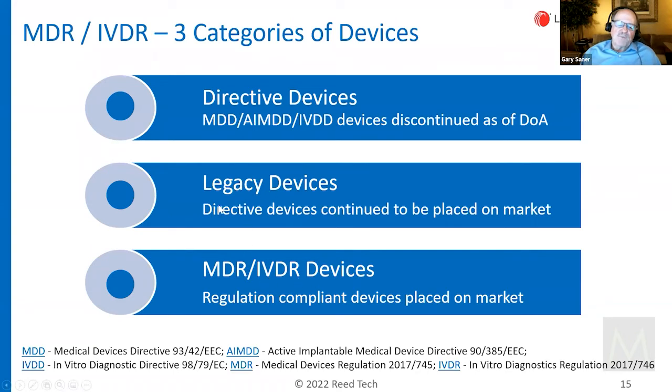So your exact same product can be applied and put into this MDR medical device regulation category. And that's called an equivalent device. So you don't make any design changes, it's physically the same, everything's identical, but now it meets the regulations. You might have to do some additional tests and get the technical documentation in place for that particular evaluation.